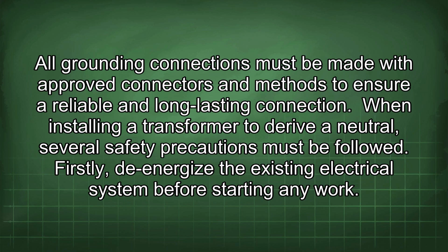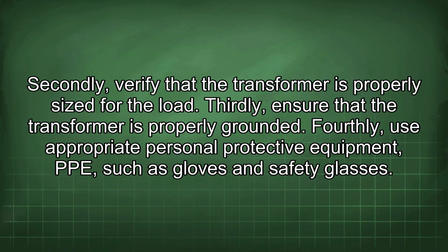When installing a transformer to derive a neutral, several safety precautions must be followed. Firstly, de-energize the existing electrical system before starting any work. Secondly, verify that the transformer is properly sized for the load. Thirdly, ensure that the transformer is properly grounded.